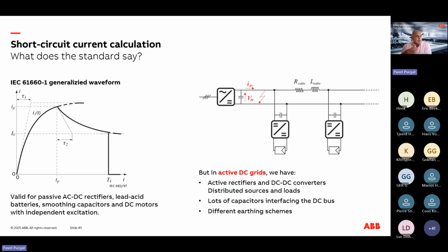Now, what happens when we have a bit more complicated DC systems, like the one we were looking at? The grid response does not necessarily need to look like this. In fact, it can be underdamped, for example, in which case the growth of the short circuit current will be sharper and the peak will be faster. But at the same time, the current can drop much sooner, which means that your protection or the trip detection unit might be too slow to even detect that you had a short circuit current. So when designing the protection, you need to also think about these types of things.